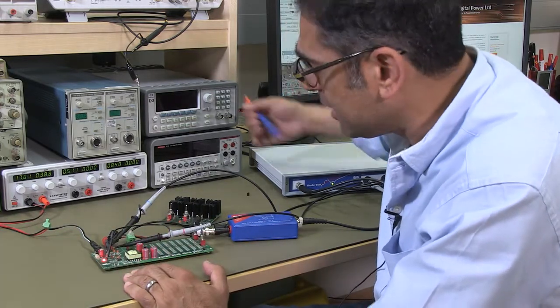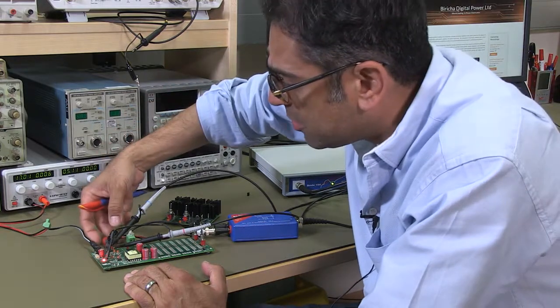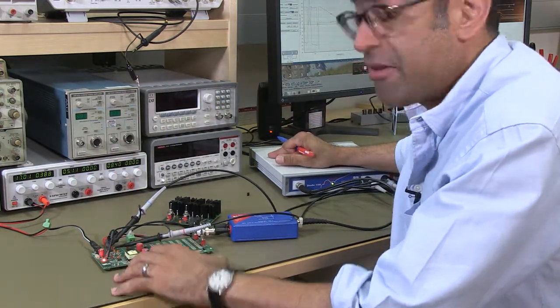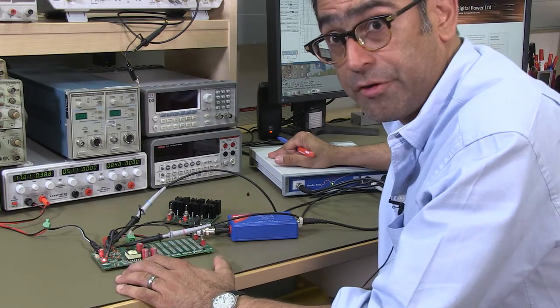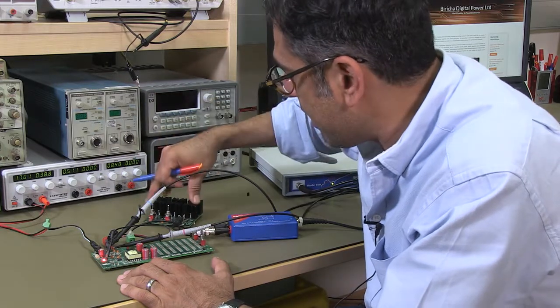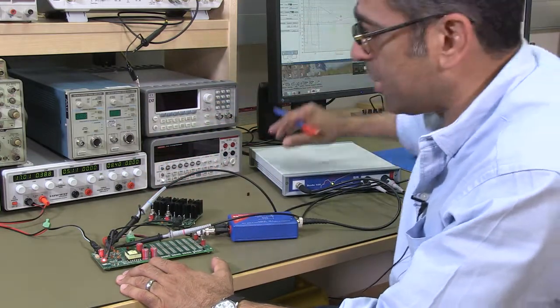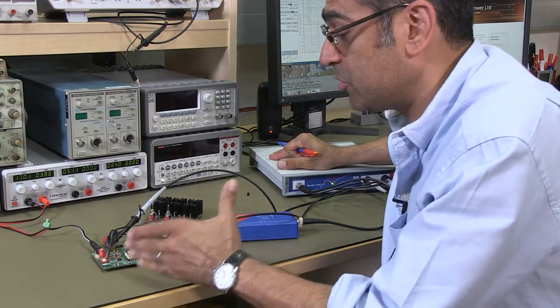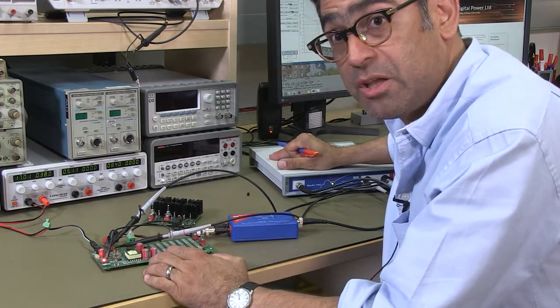I'm injecting a signal via the Bode 100 across the injection resistor and we have designed this to have a very high gain at low frequencies. The loads are set there and there, and now we're going to have a look at it on the Bode 100 to see what we are measuring with regards to the frequency response of the power supply.